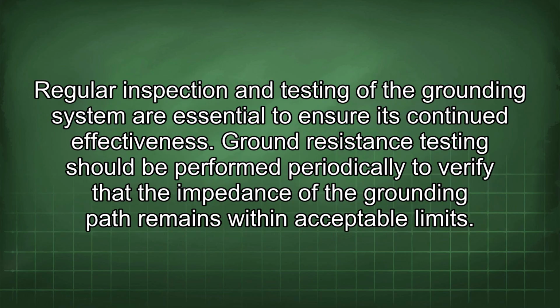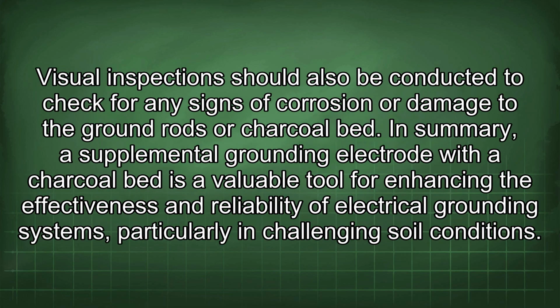Regular inspection and testing of the grounding system are essential to ensure its continued effectiveness. Ground resistance testing should be performed periodically to verify that the impedance of the grounding path remains within acceptable limits. Visual inspection should also be conducted to check for any signs of corrosion or damage to the ground rods or charcoal bed. In summary, a supplemental grounding electrode with a charcoal bed is a valuable tool for enhancing the effectiveness and reliability of electrical grounding systems, particularly in challenging soil conditions.